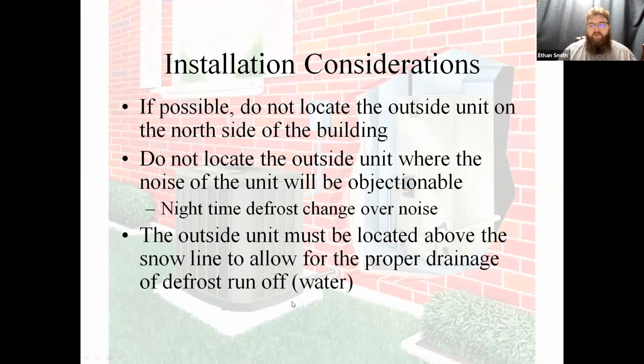We got to locate our outdoor units above frost or snow line. If you don't accumulate snow in your particular location, I still don't want to see them on the ground. I'd still rather you have at least a spacer underneath the unit, an isolation pad or something like that, just for drainage. These things do produce water when they're in defrost. If you don't have that pad elevated ever so slightly, you'll get water that'll accumulate in the bottom of the drain pan, and if it's cold enough, it will actually frost up the outside of the coils.